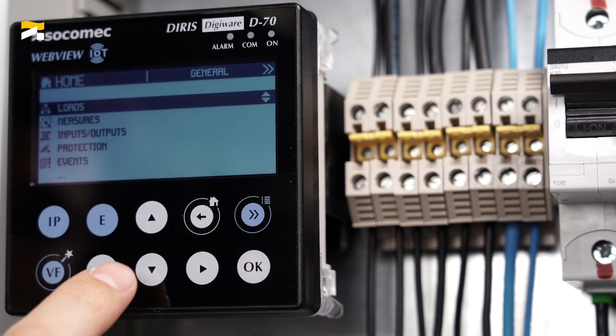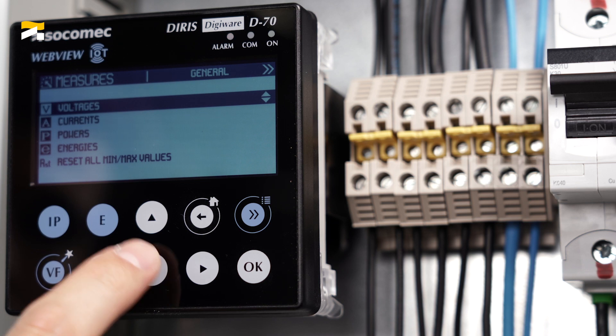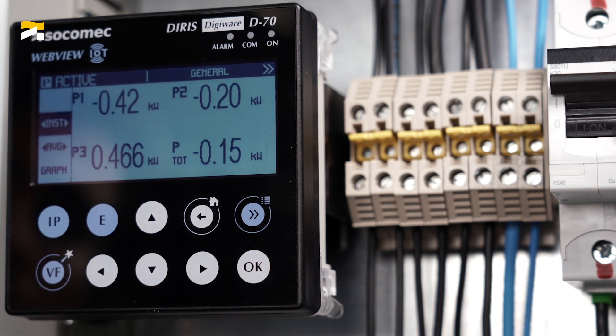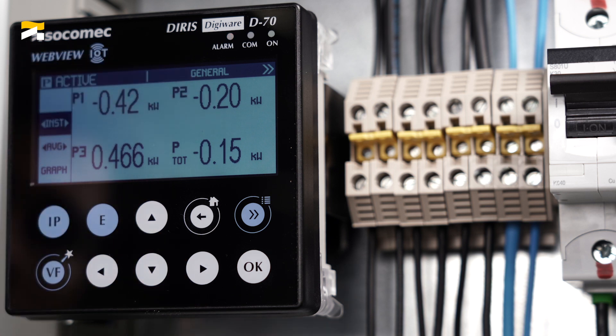Let's have a look at the real-time measurements. Active powers P1 and P2 are negative. Inconsistent readings are the direct consequence of a cabling error.